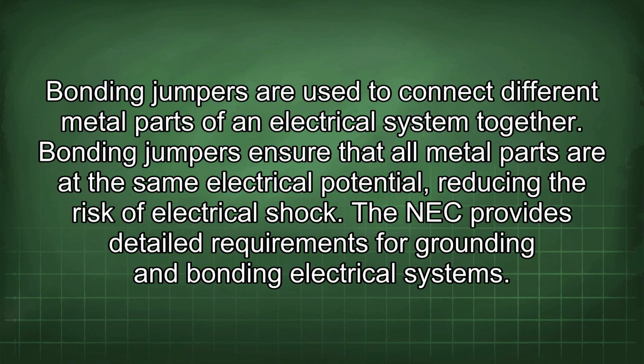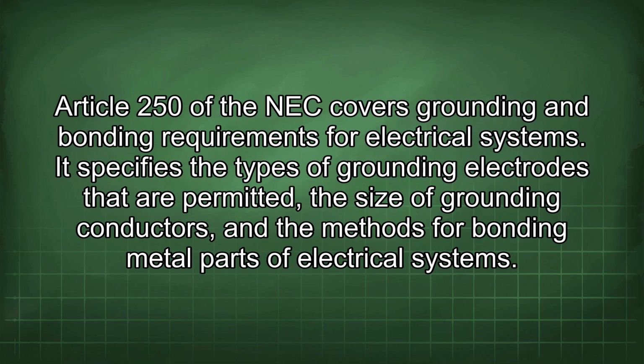Bonding jumpers are used to connect different metal parts of an electrical system together. Bonding jumpers ensure that all metal parts are at the same electrical potential, reducing the risk of electrical shock. The NEC provides detailed requirements for grounding and bonding electrical systems. Article 250 of the NEC covers grounding and bonding requirements for electrical systems. It specifies the types of grounding electrodes that are permitted, the size of grounding conductors, and the methods for bonding metal parts of electrical systems.